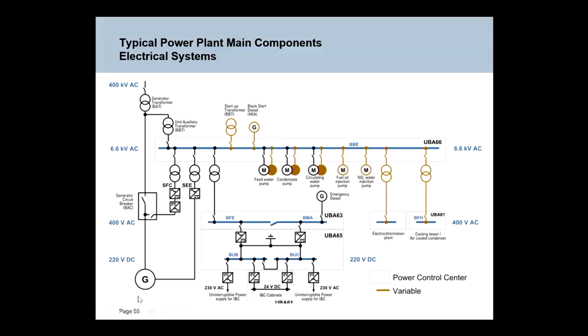So if you have a generator here on this single line diagram, a generator circuit breaker, the transformer out to the grid, and then its own supply transformer onto some switchboards that then supply motors and other transformers for other switchboards that drive all of the motors, and there are hundreds of motors on one coal-fired unit. Okay? And the motors will be at different voltage levels. So big motors will be supplied at 11 kV and 6.6 kV. Smaller motors at 415 volts in Australia. So motors up to about this size will be 415 volts.